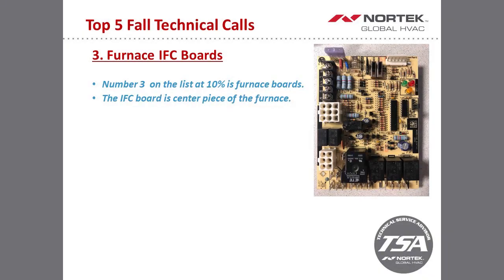Just keep in mind that board is the heart of the furnace. So on your 9-pin or your 12-pin plug from a low voltage standpoint, that's where all your safeties and pressure switches will plug into. You'll also have a 6-pin plug for your inducer and your igniter portion of that. The biggest thing that we tell guys is to try to know the sequence of the furnace, because that is very important in regards to troubleshooting. If you know the sequence, the startup of a G7 furnace, that will greatly help you in troubleshooting.